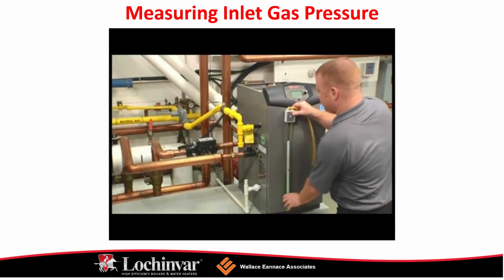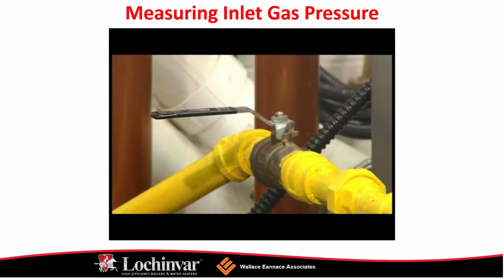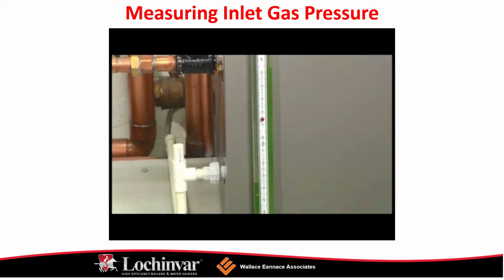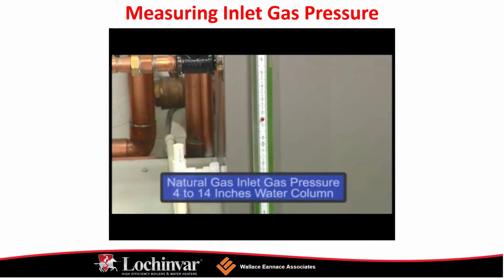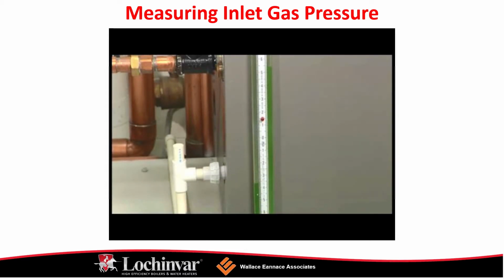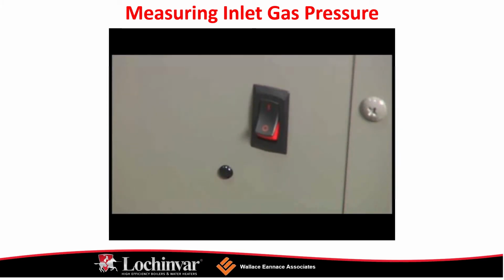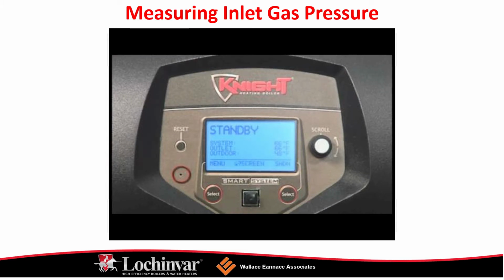The information contained in this video is intended as an aid to a qualified installing contractor or service technician. It is not intended to replace the installation or service manuals that are supplied with the equipment. Locate the on-off switch on the back of the unit. Turn the switch to the off position. Turn off the main gas supply to the unit at the external main manual gas valve. Grasp the top panel at the front lower edge. Lift the panel up and pull it away from the unit. Locate the inlet gas pressure tap on the gas valve. The pressure tap will be the first connection on the gas valve.